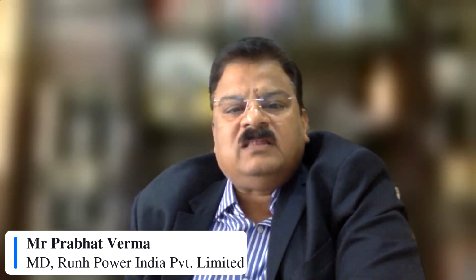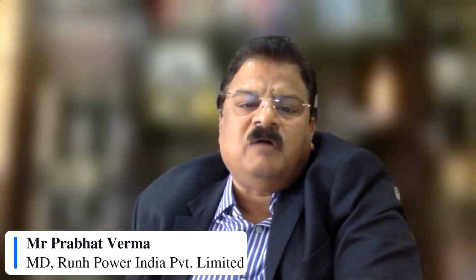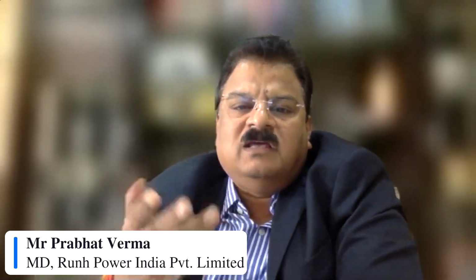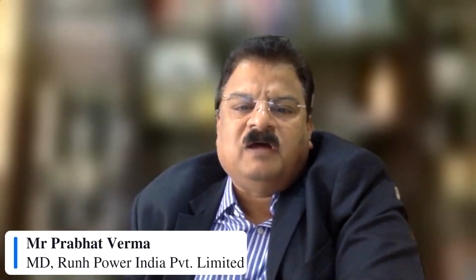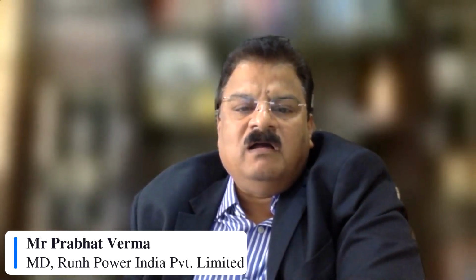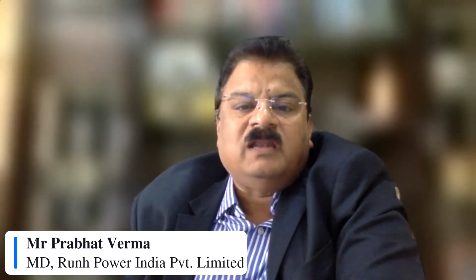His other question is, what is the impact on heat rate loss and performance in boiler and TG if the load is increased and reduced by 20? Same thing, yes, 20 megawatt. All right. So, Sanjeev, I think you got the answer from our expert from TCE. No, he says it's a PF boiler. Okay, all right. Though we presented some numbers for higher capacity units, 600 and 800, we can evaluate for 125 megawatt also. Of course, I think it's a reheat unit only, because generally we go for reheat boilers above 120. So we can calculate and estimate what the impact would be.